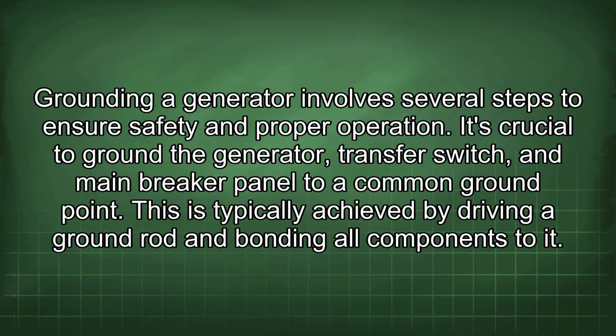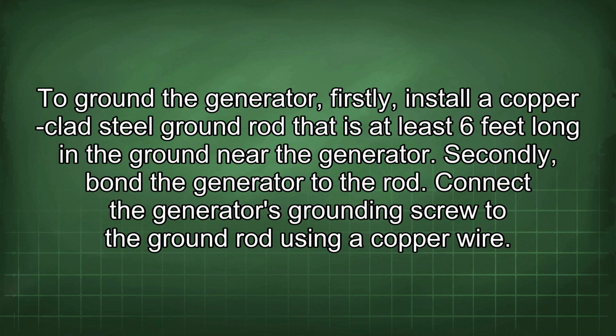Grounding a generator involves several steps to ensure safety and proper operation. It's crucial to ground the generator, transfer switch, and main breaker panel to a common ground point. This is typically achieved by driving a ground rod and bonding all components to it. To ground the generator, firstly, install a copper-clad steel ground rod that is at least 6 feet long in the ground near the generator. Secondly, bond the generator to the rod.